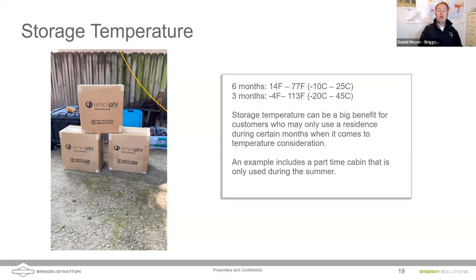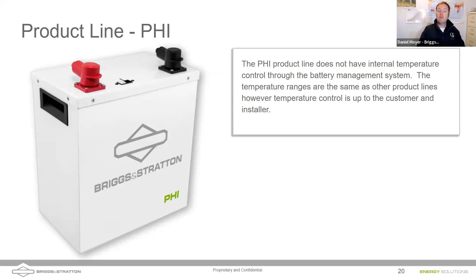Keep in mind that the Phi battery does not have an internal temperature monitoring system that can communicate to an external piece of equipment. So it's really important that we adjust the programming on different inverters and charge controllers so that we're setting them up. Some inverters do have that temperature compensation.